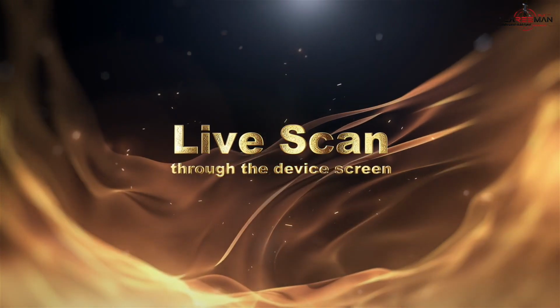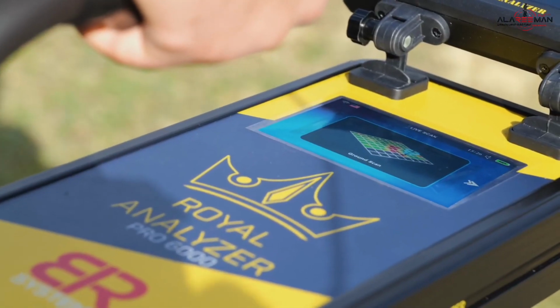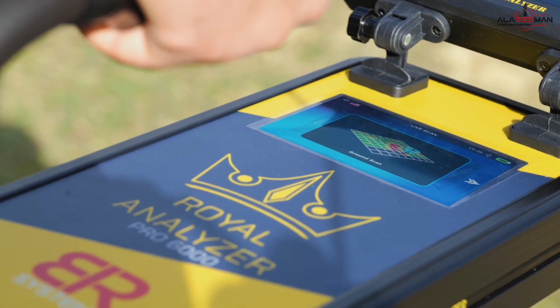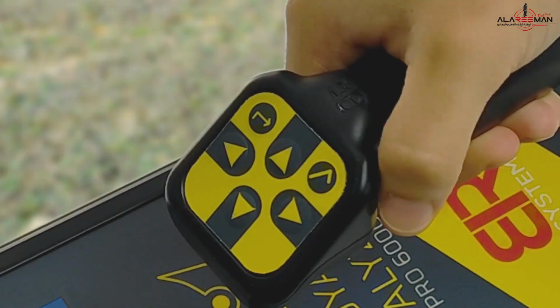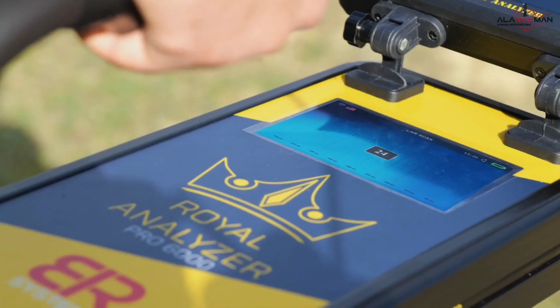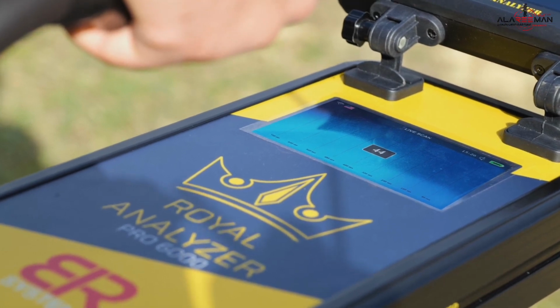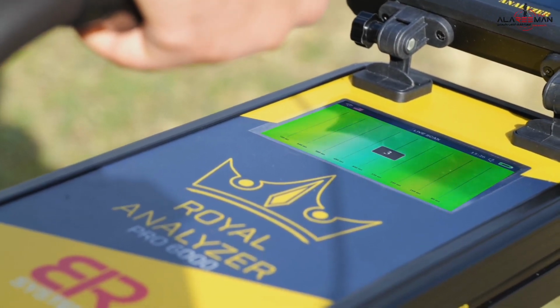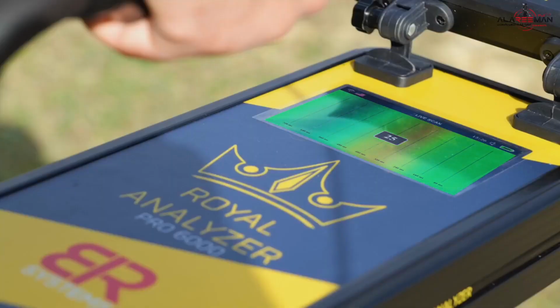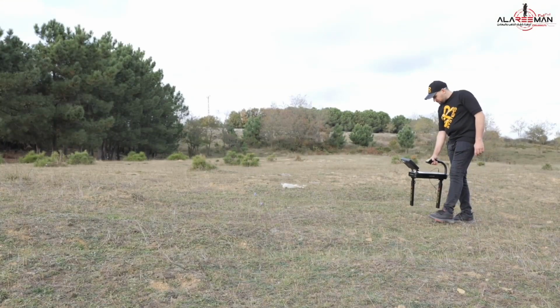3. Live Scan through the device screen. Choose Live Scan from the device screen using the navigation buttons. Press the Enter button. The device starts beeping. Wait 10 seconds. Press the Enter button again for the device to self-calibrate, after which the sound stops and the screen color changes to green. Then the device becomes ready for the scanning process.